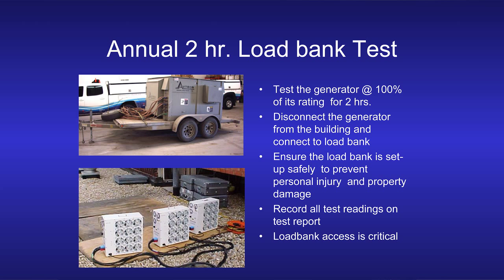Again, these are what load banks look like. The top one in the picture is a 1200 kilowatt load bank, so we use that on the larger sets, and on the smaller ones you see 3 of the 100 kilowatt. They're actually quite portable, so they can be taken up to the roof, which is where I think this picture was taken, on somebody's roof. But the cabling is quite a job sometimes, depending on where the generator is compared to where we can put these things outside. They generate a lot of heat. They're giant toasters, so you can't have the heat going back into the building.